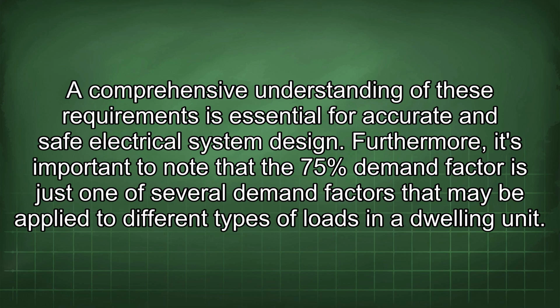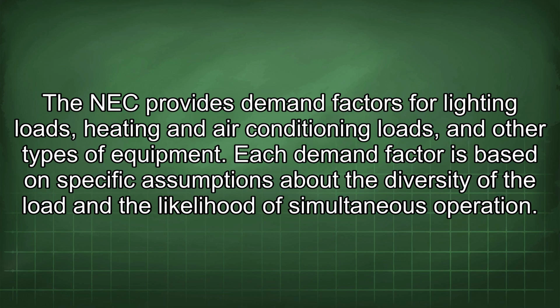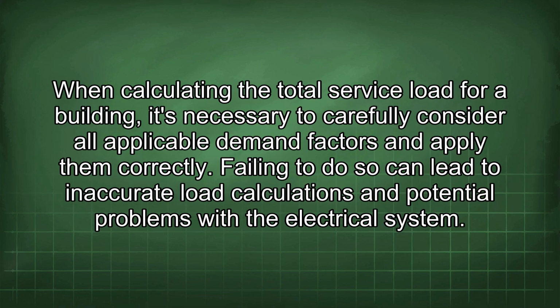Furthermore, it's important to note that the 75% demand factor is just one of several demand factors that may be applied to different types of loads in a dwelling unit. The NEC provides demand factors for lighting loads, heating and air conditioning loads, and other types of equipment. Each demand factor is based on specific assumptions about the diversity of the load and the likelihood of simultaneous operation. When calculating the total service load for a building, it's necessary to carefully consider all applicable demand factors and apply them correctly. Failing to do so can lead to inaccurate load calculations and potential problems with the electrical system.